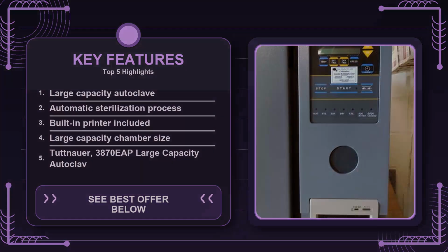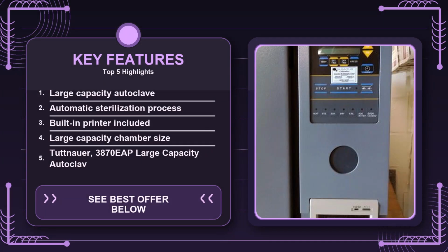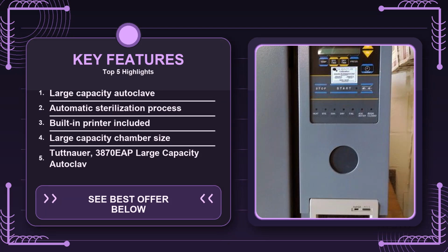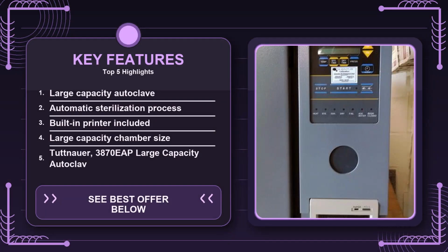To sum up, the Tuttnauer 3870EAP large-capacity automatic autoclave with printer is a solid, workhorse-type piece of equipment that shines when you need high throughput and detailed record-keeping. Its strengths lie in the spacious chamber, the integrated printing for compliance, and a service network that's familiar to many professionals. The trade-offs are the larger footprint, longer cycle times compared to rapid heat competitors, and the ongoing cost of printer consumables. If those trade-offs line up with the way you run your practice or lab, the investment makes sense. If they don't, you'd be better off scaling down. Either way, do the math based on how many cycles.